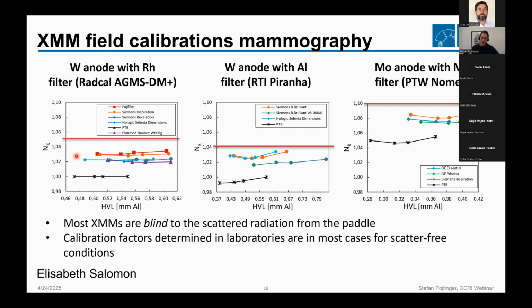One of the reasons we see why these calibration factors differ for the XMMs between laboratory conditions and clinical conditions is that the XMMs are technically blind for scatter radiation. Here we are talking only about mammography, and in mammography we were putting the paddle of the mammography device on the RC6M ionization chamber because we wanted to measure the radiation that is also seen later by the patient. And of course, an ionization chamber, especially the RC6M with a thin entrance filter, will see that scattered radiation.